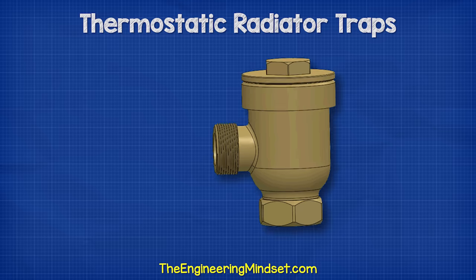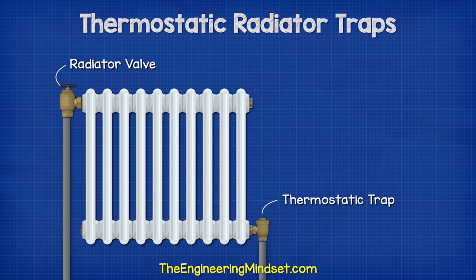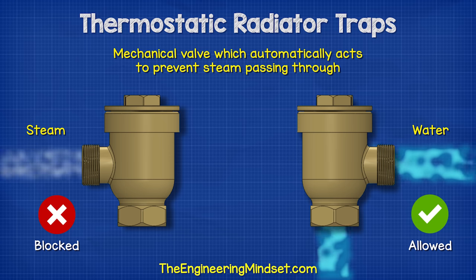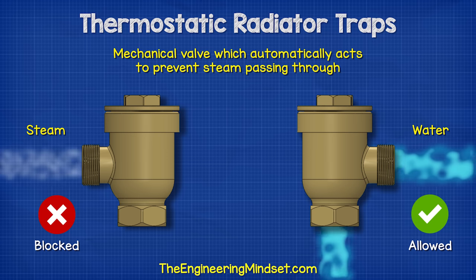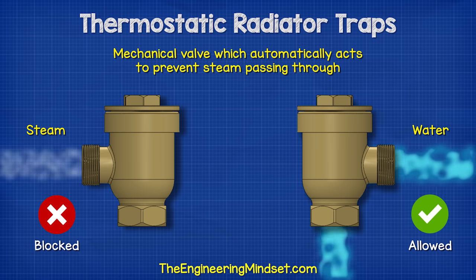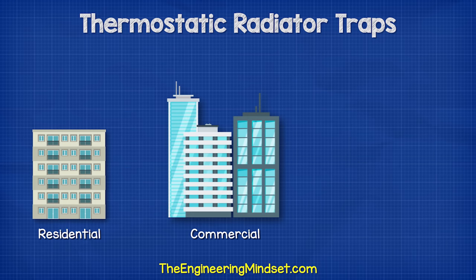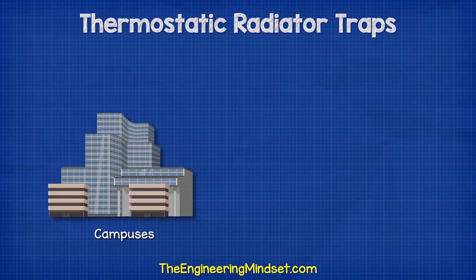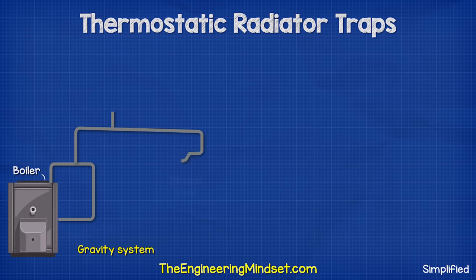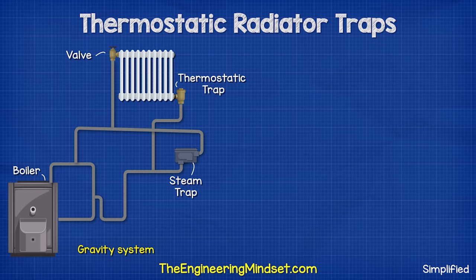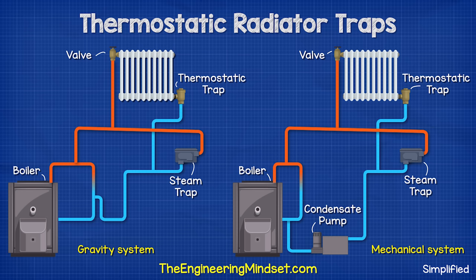The thermostatic radiator trap looks something like this, although there are many variations. These valves are connected to the low side of a steam operated radiator. This is a mechanical valve which allows air and water to pass through but automatically acts to prevent steam passing through. Steam heating systems can be found in residential, commercial, and even industrial sites. They're very common in large campuses, especially larger older buildings. These systems do not require pumps — instead they use the steam itself to distribute heat around the building, although we might find a condensate pump on the return line.